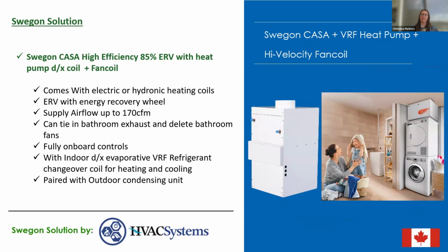This ERV uses an energy recovery wheel, so that's how it controls the humidity. The unit I've selected supplies airflow up to 170, but we'd have to dive into the loads exactly. Nice thing about this one is it can tie into your bathroom exhaust and delete all your bathroom fans. This one comes with fully onboard controls, and then you would have your indoor DX evap coil plus your outdoor condensing unit.